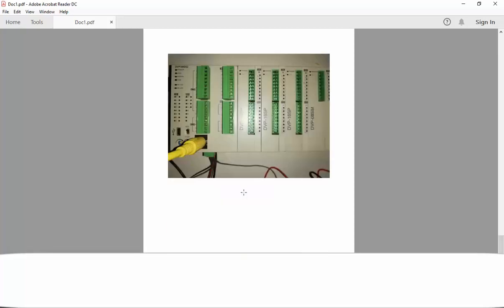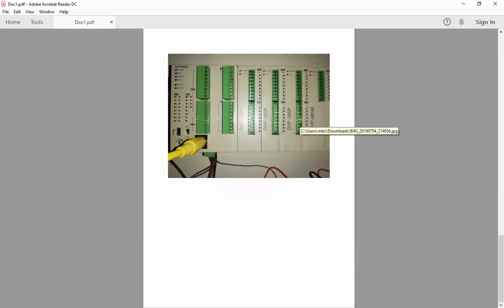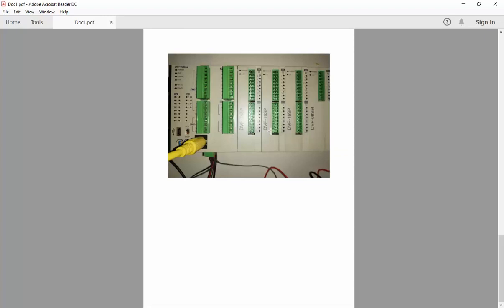What about if we connect another extensions? For example, another two DVP16SP, so now we have three DVP16SP and DVP08SM, this is just represent the inputs. So you can see here we have the number of outputs, the number of outputs is eight multiplied by three, so it's 24 and the number of inputs is I think 32 inputs.